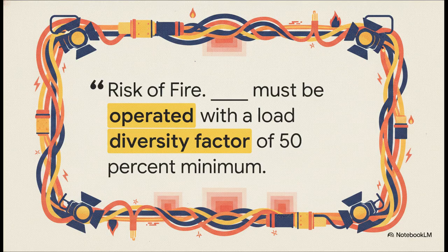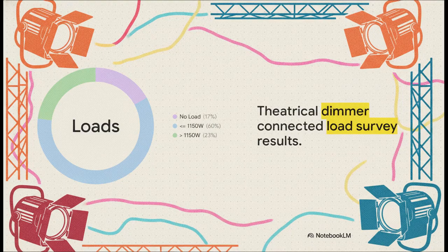But it secretly demands a massive trade-off. It legally requires that you only turn on half the circuits at any given time, or at least ensure the total load never exceeds 50% capacity. You literally cannot run everything at 100% simultaneously without risking a fire. So you might be wondering, if lighting designers don't always know about this hidden rule, why haven't theater cables been melting down for decades? Well, it basically comes down to historical luck.